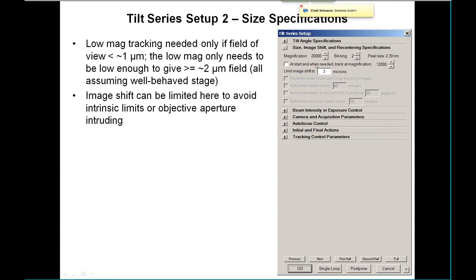The low mag tracking option is not needed very often. It's needed if the field of view you're working with is less than about a micron, where tracking is not very good as you go from one tilt to another. The low mag you specify here only needs to be low enough to give about two microns or more of image view. This all assumes a well-behaved stage — with a very poorly behaved stage, this could become a tool even at normal magnifications, but typically it's used for higher magnifications.